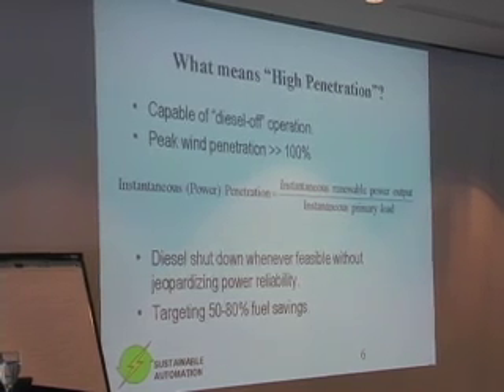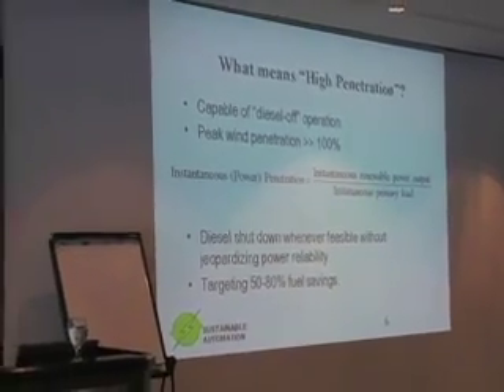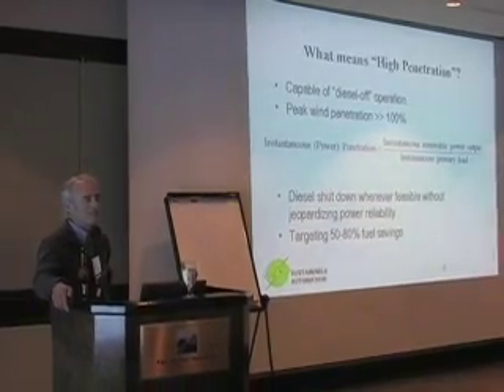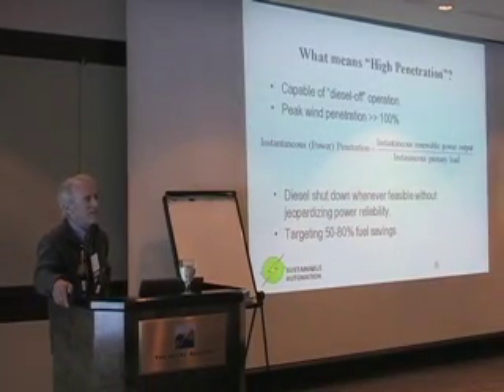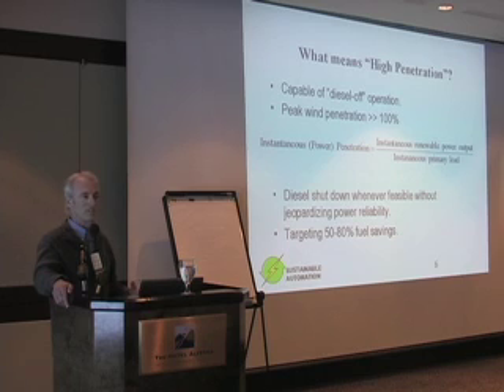So there's the phrase high penetration in the title. Russell just talked about that briefly. I have somewhat of a different definition, although we both speak in terms of instantaneous wind penetration. He didn't get how you could have over 100%. Well, by my definition, which is the instantaneous renewable output, in this case wind, divided by the instantaneous load, well, it's easy to see that you can have quite a bit more wind power output at any given moment than you have load, which means, by my definition, that you can have wind penetrations well in excess of 100% at any given time.